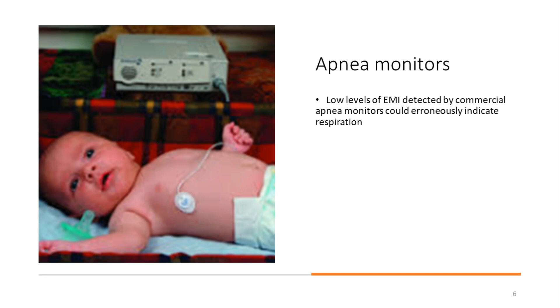Another case was of apnea monitors. There was a problem in the earlier apnea monitors where they erroneously indicated respiration for some low levels of EMI which were detected. Now, a physician at a major university hospital reported that apnea monitors would not work in some surrounding neighborhoods. It all depended upon what neighborhood you would be using it in. So a unit cannot work in that manner. It has to work in all kinds of environments. Prolonged sleep apnea is detrimental to adults and can be fatal to infants. Other reports of monitor failures prompted the FDA to conduct tests. The conclusion was that low levels of EMI detected by commercial apnea monitors could erroneously indicate respiration, and they had to recall all those monitors.